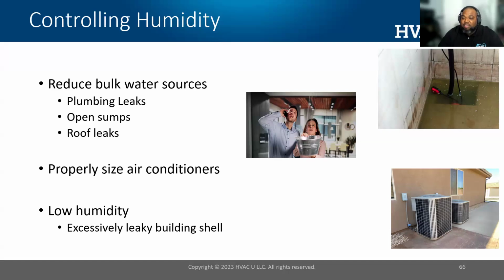Well, if you have an excessively leaky building shell, it will make the air drier because it's displacing all the moisture that's inside the building and pushing it outside due to the difference in temperature between inside and outside. We will purchase a humidifier to put water vapor back into the air, only to have it be displaced again by a leaky building shell. So you want to look at the whole entire house as a system to help understand the IAQ issues.